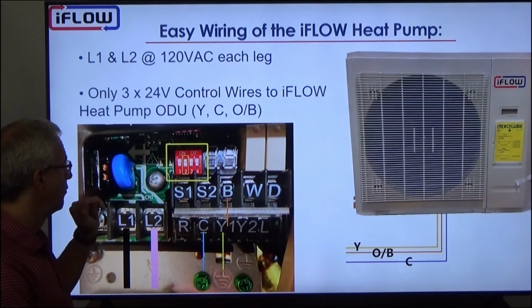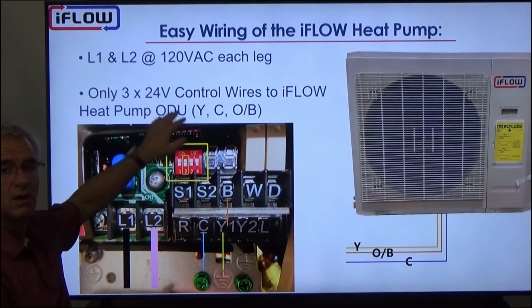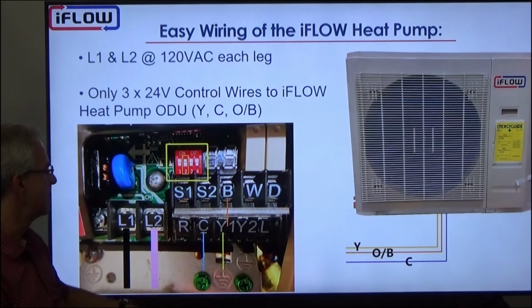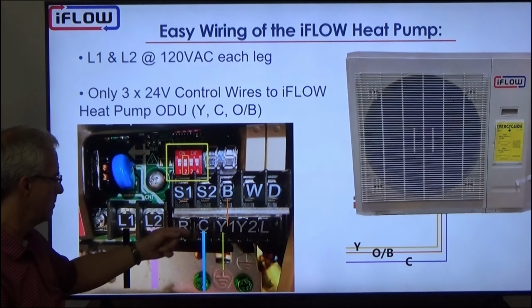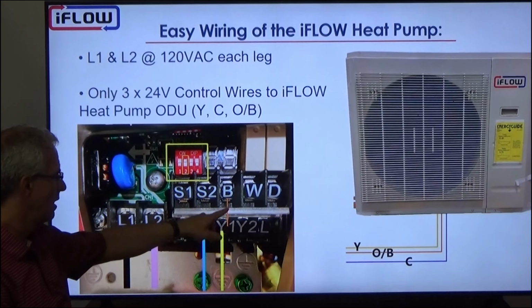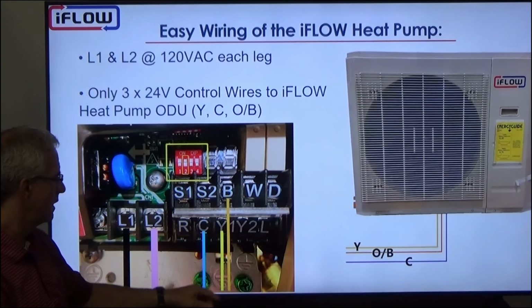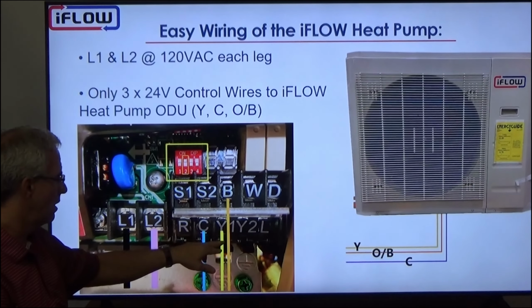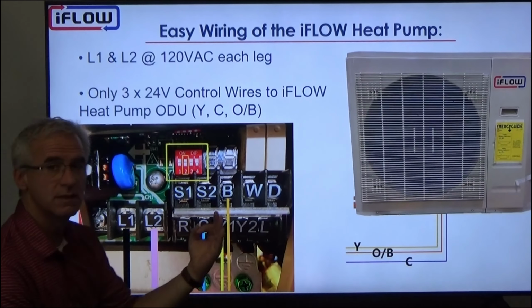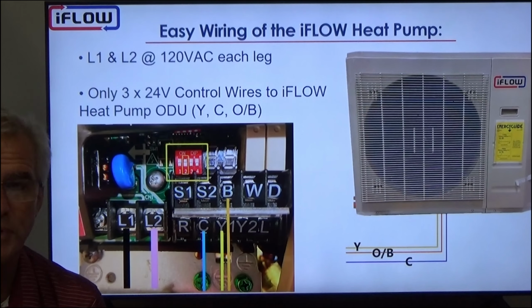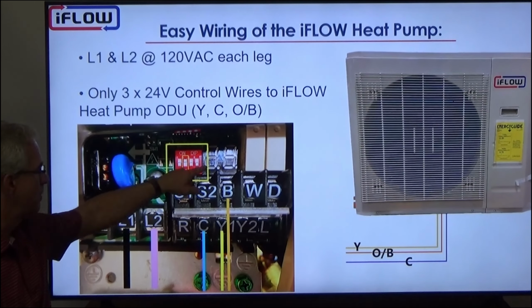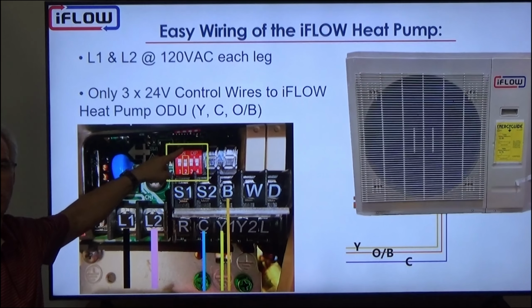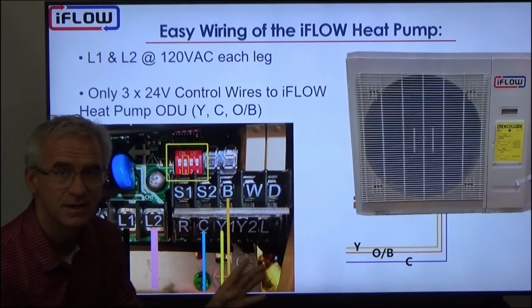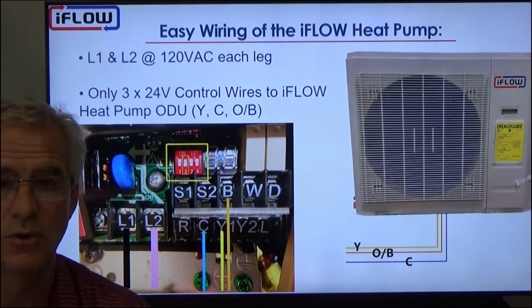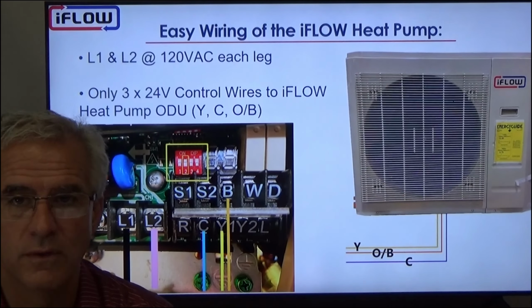And then we have our low voltage wire. So only 3 of the low voltage wires we will have in that system. So we'll have our C wire, we'll have our Y wire, and then we'll have our B wire, right? So our common, our cooling, and our heating. So that's it, 3 wires. That's as simple as it needs to be. Nothing complex about it. The only other thing, we have a bank of dip switches. Dip switch number 2 moves to the up position. That is really it in terms of wiring the outdoor unit. You don't need anything more than that.